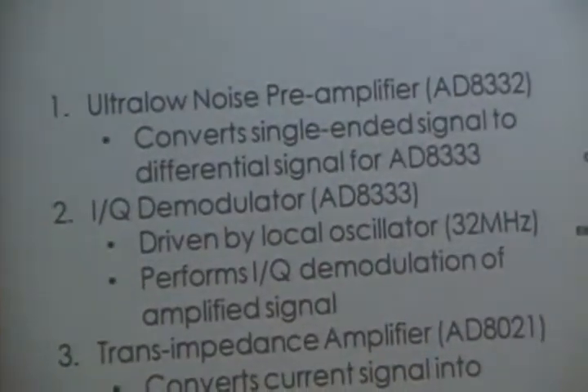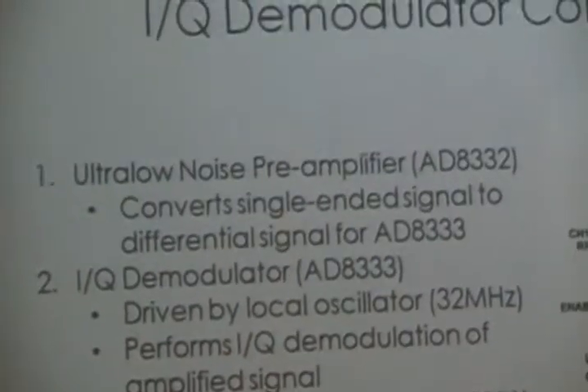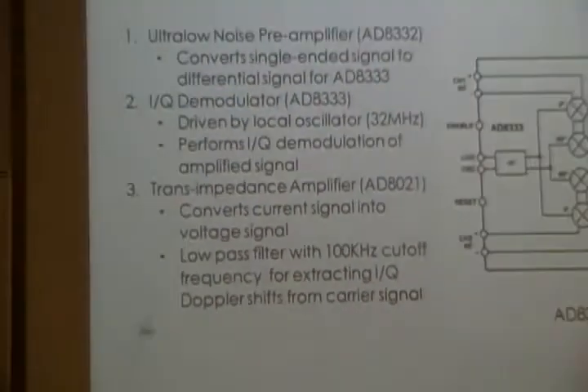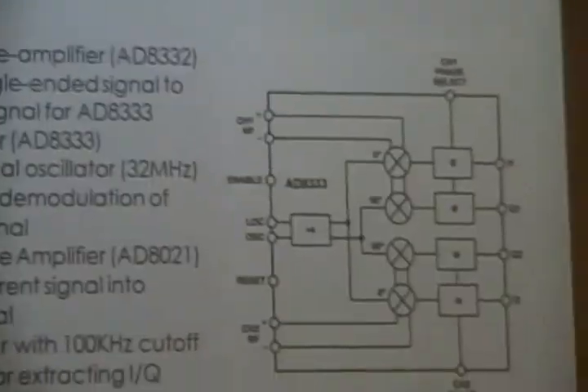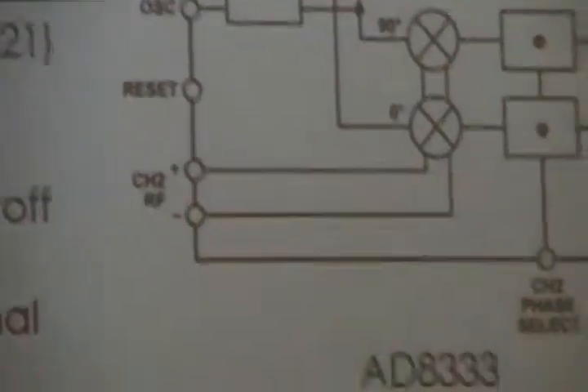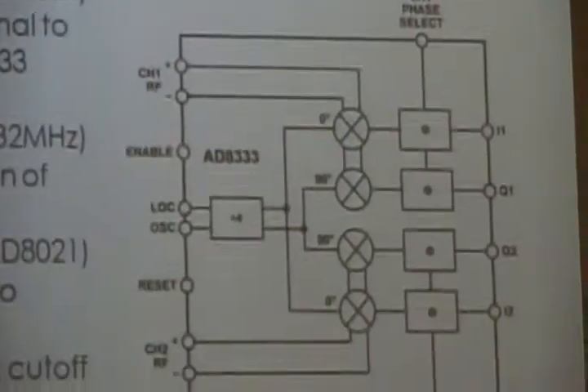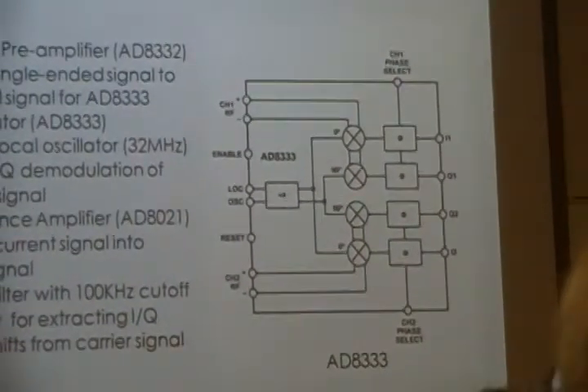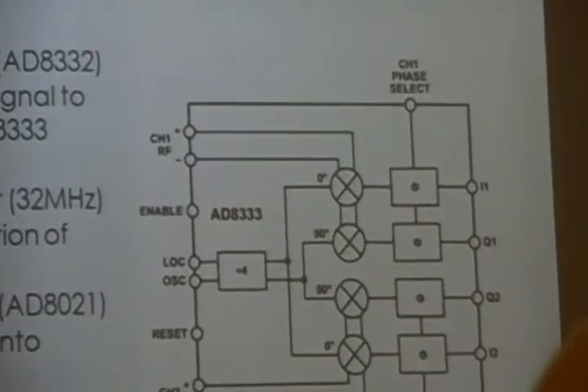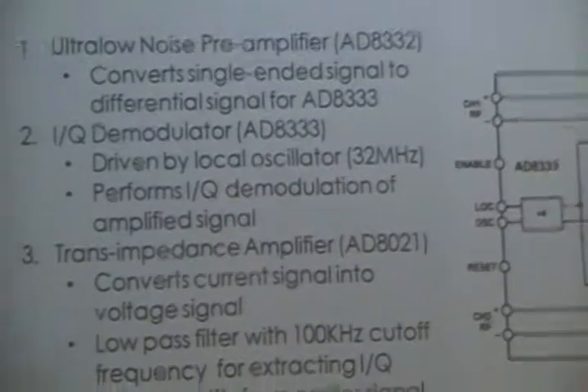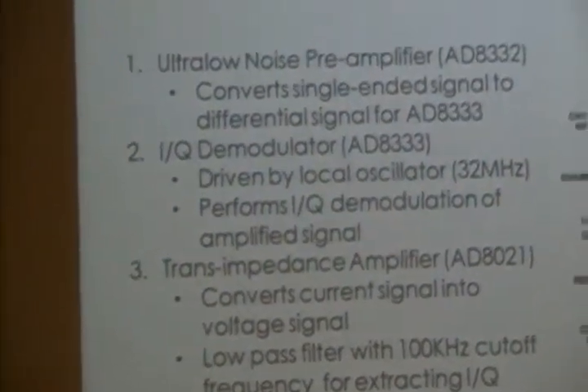This is our components for our IQ demodulator, which has a low noise pre-amplifier that gets the single-ended modulated signal and turns it into a differential signal that is passed to our demodulator, which performs IQ demodulation along with a 32 megahertz signal. The reason we're using 32 is we divide by 4 to get our carrier signal and a 90-degree phase shifted version of our carrier signal. This is then passed to our transimpedance amplifiers, turning the currents from the demodulator into a voltage, and acting as a filter as well to get our I and Q values.